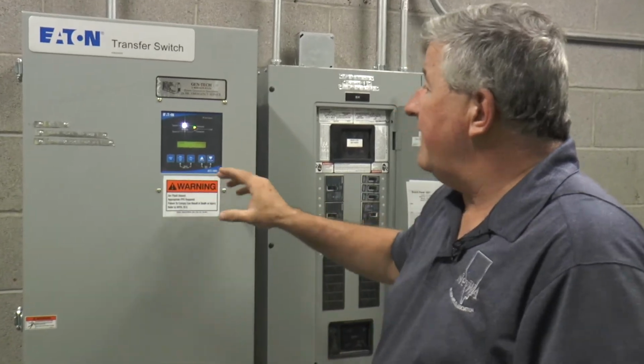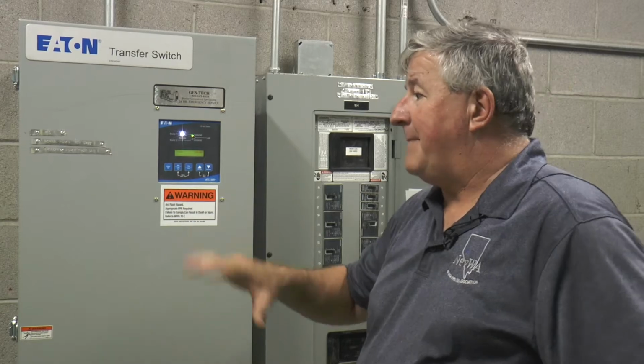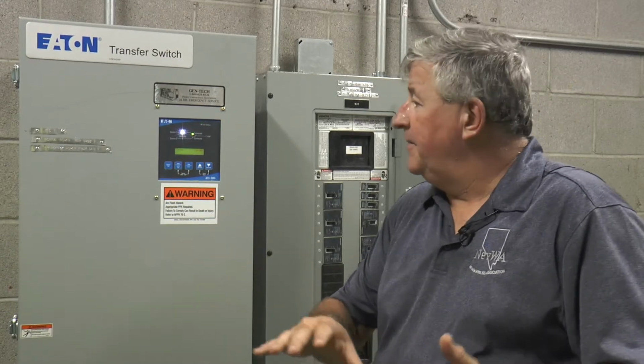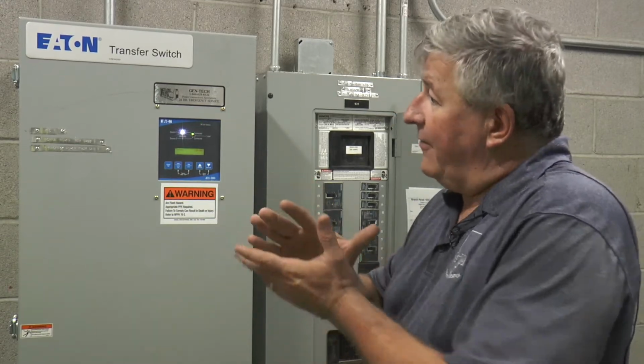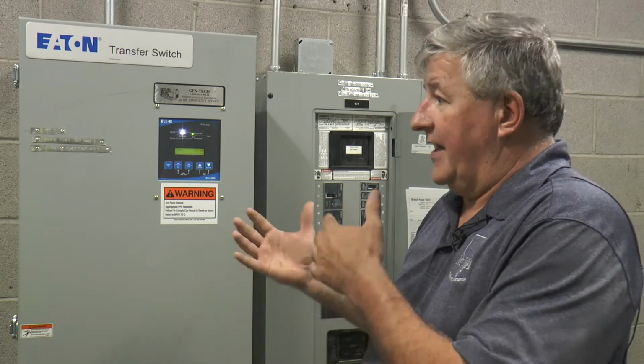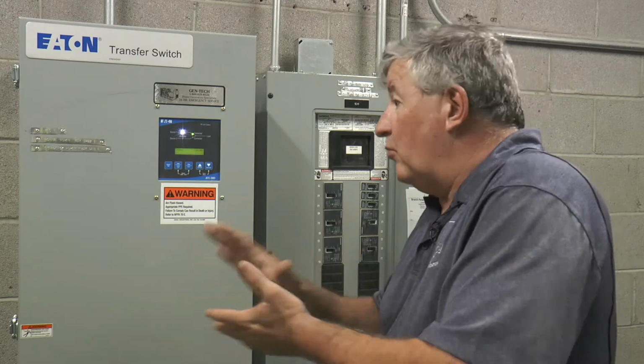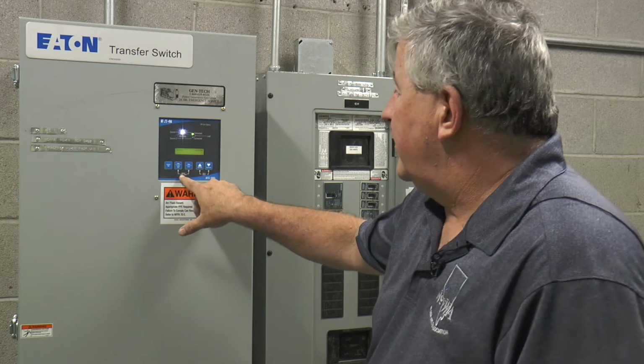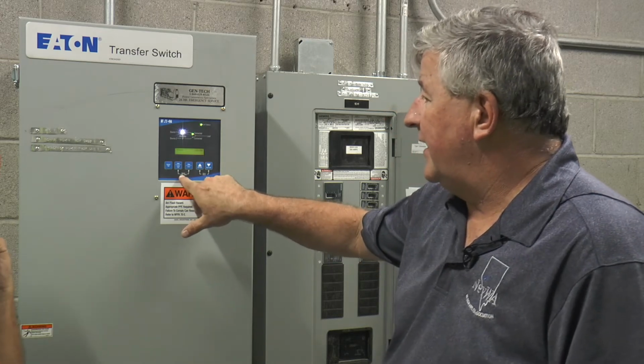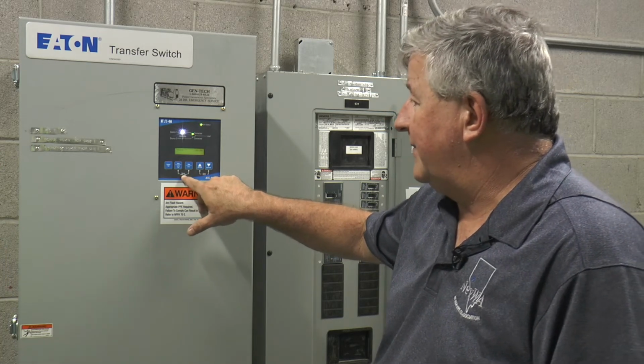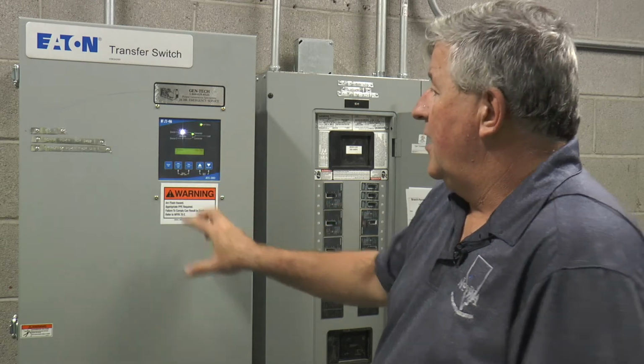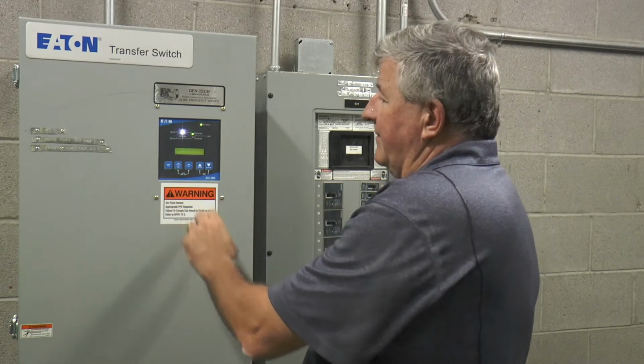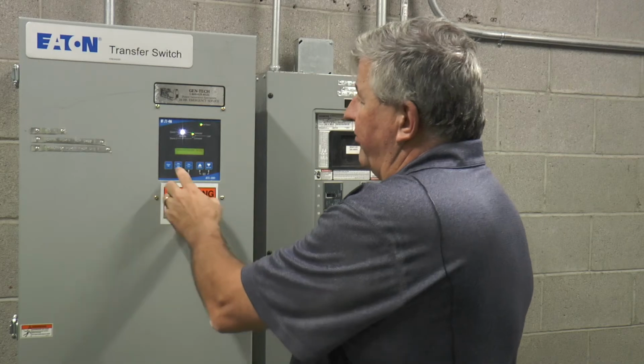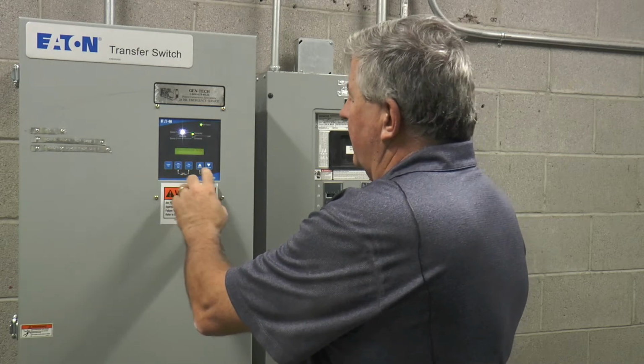If you wanted to bypass that time delay, and you said, okay, I want the utility back on, I have other functions I can't, or whatever the cause, there is a function here: bypass time delay normal to emergency and time delay emergency to normal. You push both those buttons at the same time and it will just go through, and let me clear that.